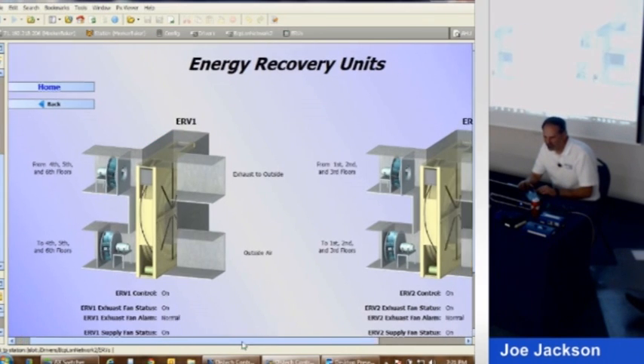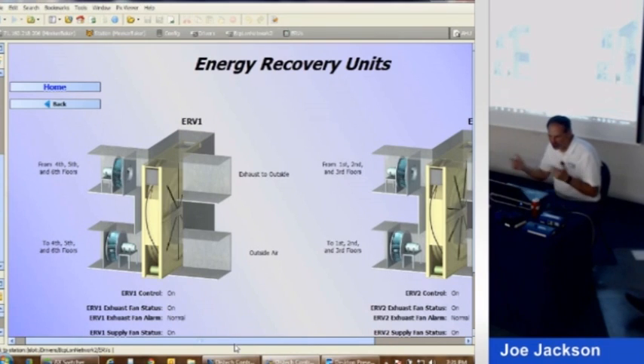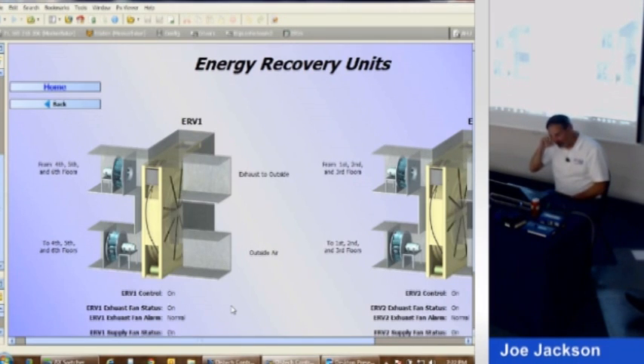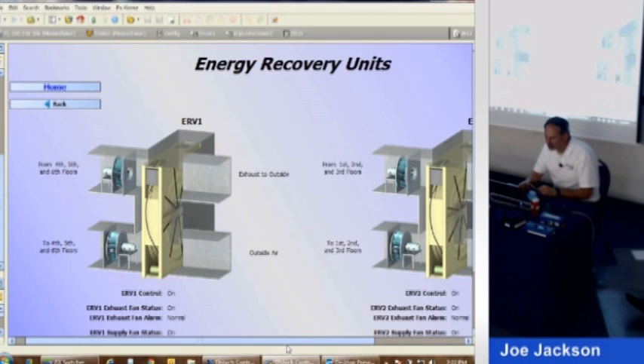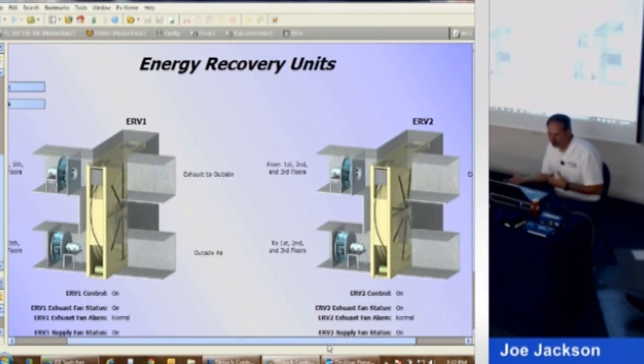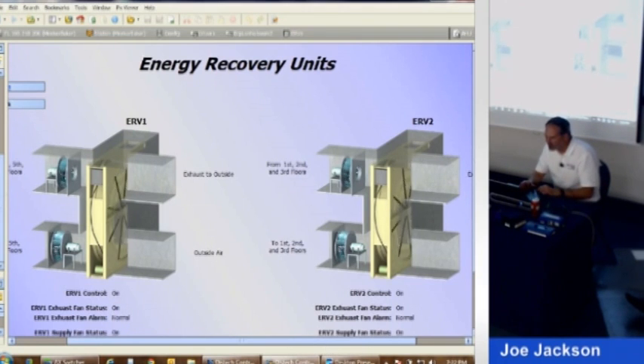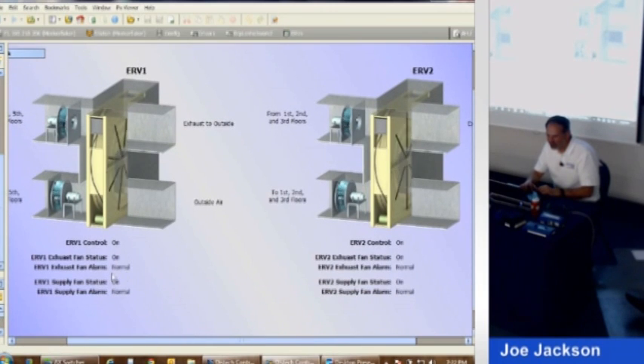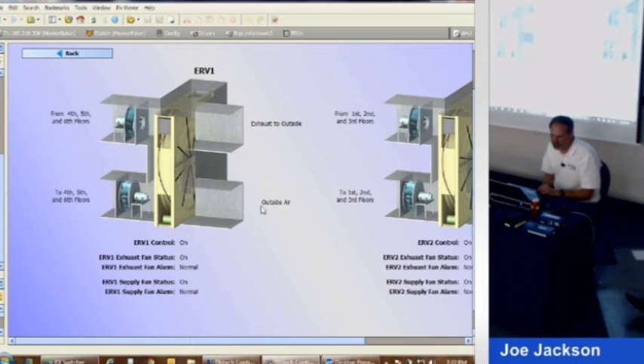We've got a couple of energy recovery ventilators. Since the heat pumps don't have any outside air on them, we got a couple of these guys. We're blowing in outside air and then blowing the exhaust back out, pulling it out of the restrooms actually. So it's all relatively low cost to bring this air in because we're preheating it or pre-cooling it by the exhaust air. We can see the fan statuses, both of the supply and the return fans, supply and exhaust fans. Real simple little units. We can see the heat wheel turning on it. Again, real easy, but nice to know that the equipment's working.